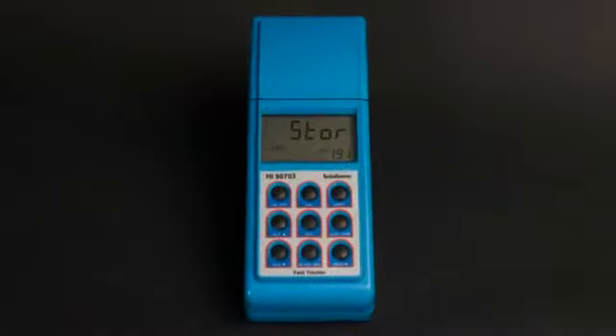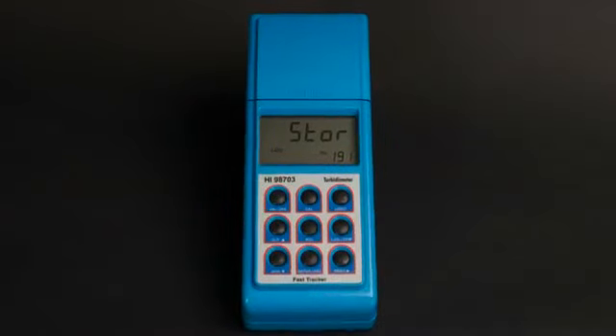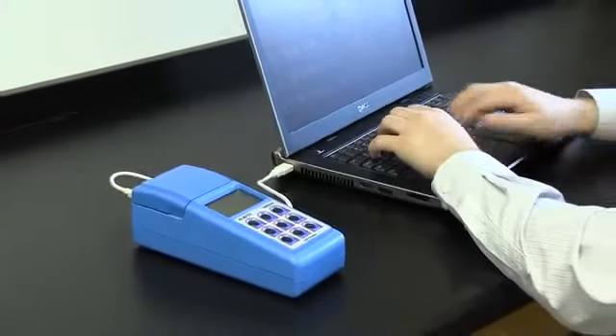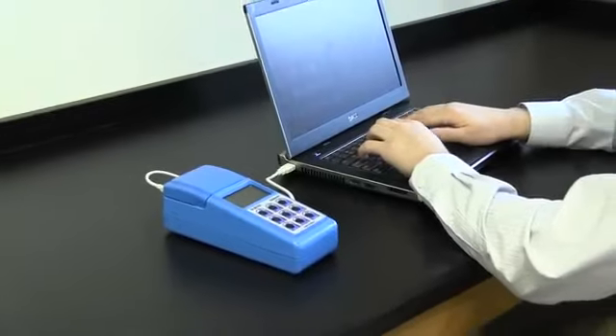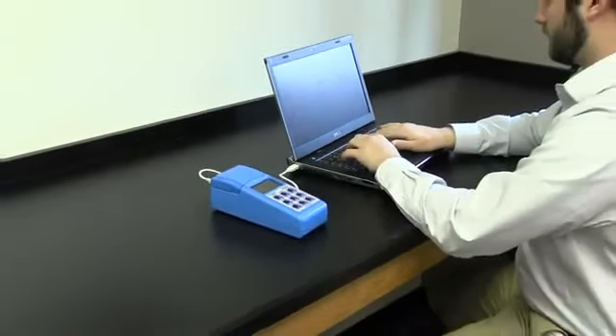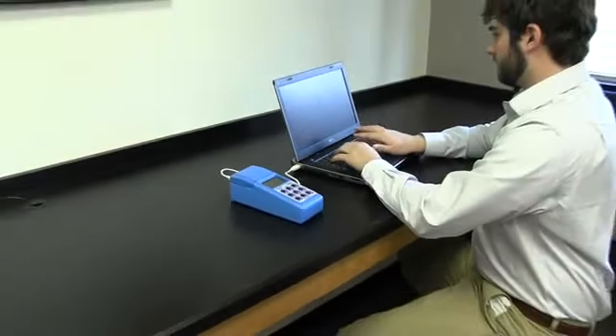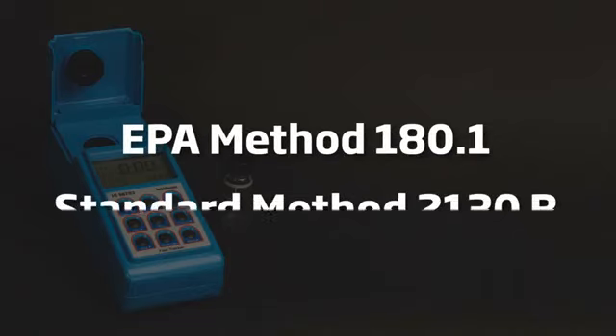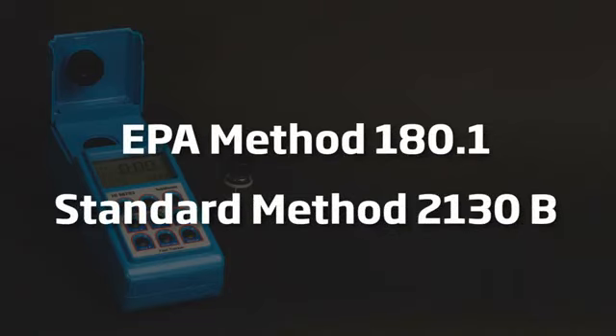It can record up to 200 measurements, which can later be downloaded to a PC for analysis. The HI-98703 meets the requirements for both EPA Method 180.1 and Standard Method 2130B, making it an ideal meter for testing wastewater or drinking water.